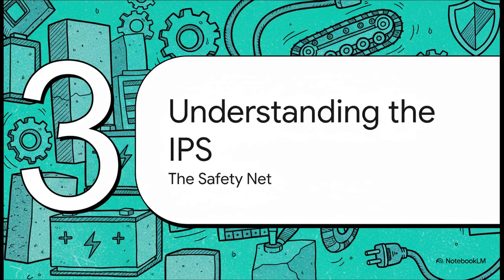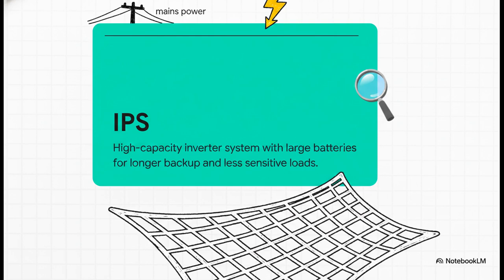Moving right along to Section 3, understanding the IPS. Now, while the UPS is a precision instrument, the IPS is built for a totally different kind of endurance. An instant power supply, or IPS, is a high-capacity inverter system paired with large, robust lead-acid batteries. While it's functionally similar to a basic standby UPS, it's generally designed for much longer backup durations and less sensitive loads. If the UPS is an active shield constantly blocking hits, I want you to think of the IPS as a safety net. The IPS relies on the raw mains power for as long as it possibly can, and it only springs into action to catch your equipment once the utility power has actually fallen away.